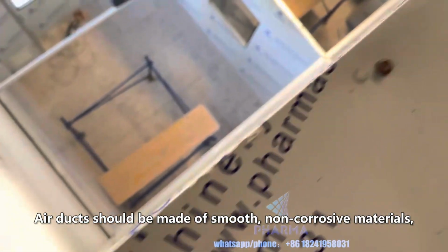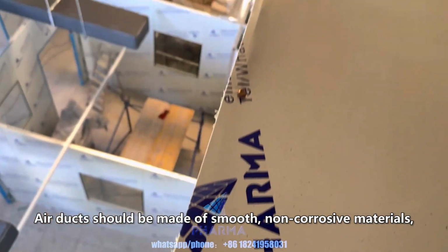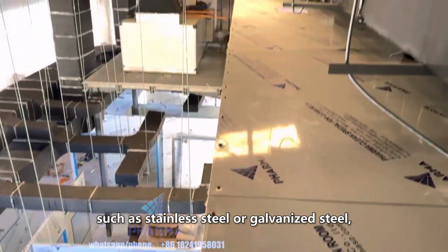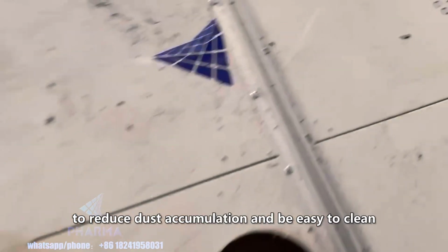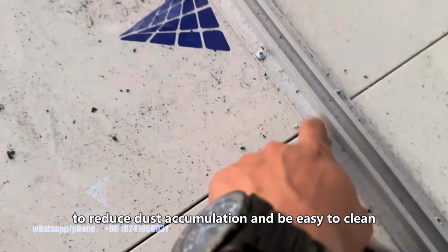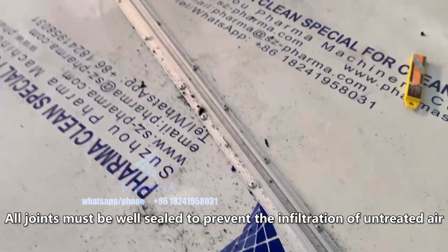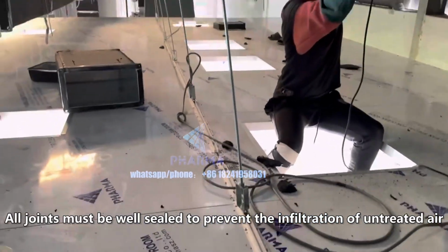Air ducts should be made of smooth, non-corrosive materials, such as stainless steel or galvanized steel, to reduce dust accumulation and be easy to clean. All joints must be well sealed to prevent the infiltration of untreated air.